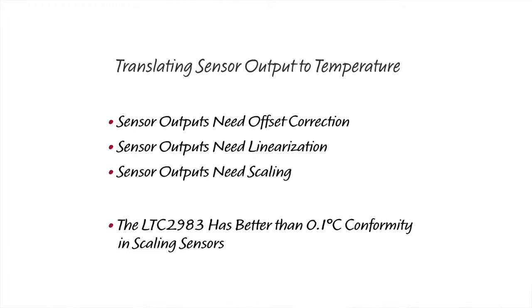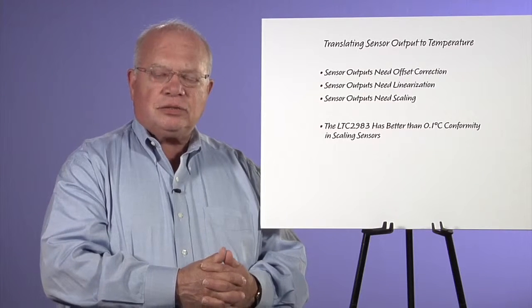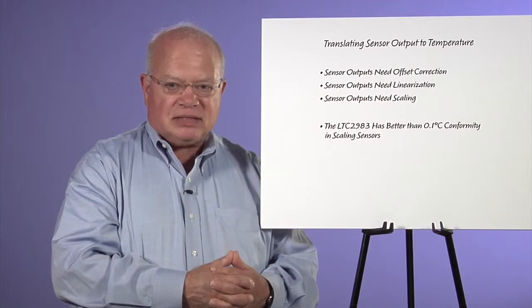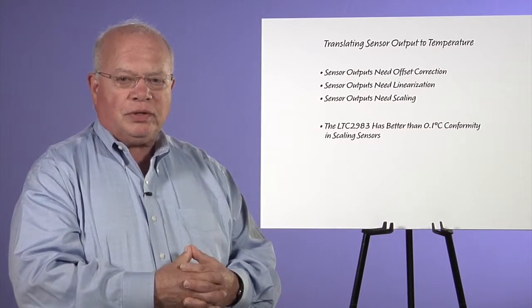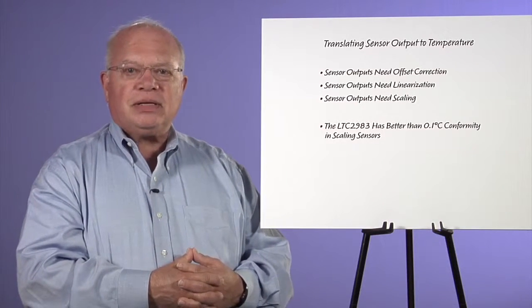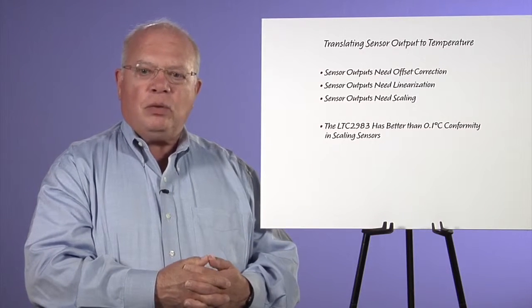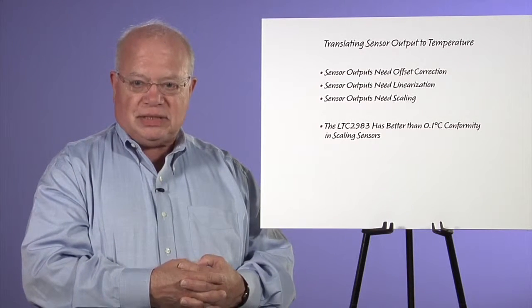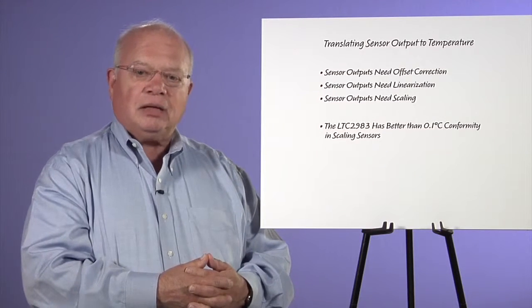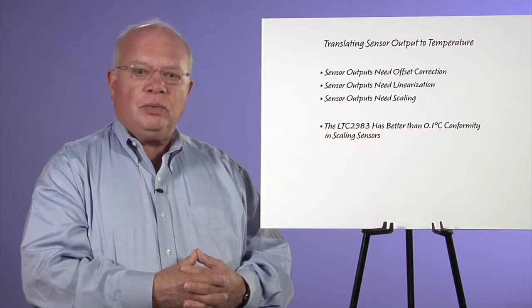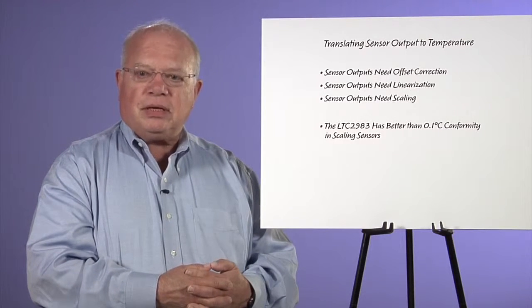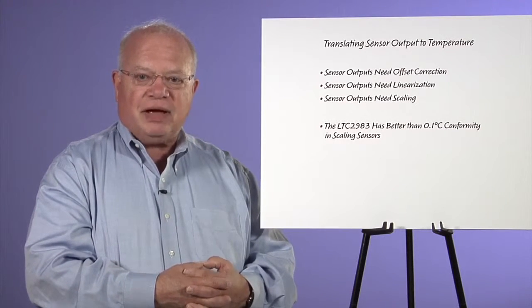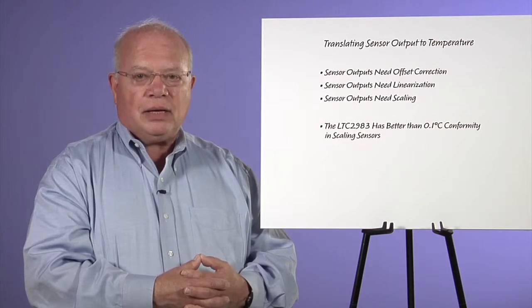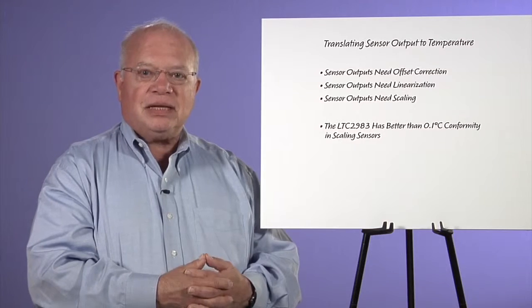So we aim to get the best accuracy we can in the electronics so that we throw all the inaccuracy back into the sensor. We call our device 0.1 degree C accurate, but it's really 0.1 degree C conformity because we can't tell you what the sensor accuracy is. We have a lot of sensors come with calibration tables. We have some RAM in our processor so that you can put in custom linearization and scale factor for the different sensors. And you can end up with much better accuracy than the as manufactured sensors will give you.